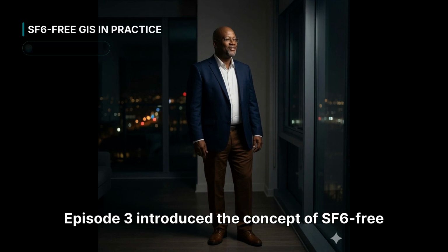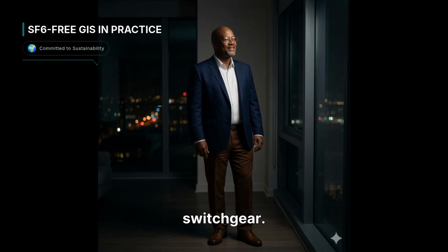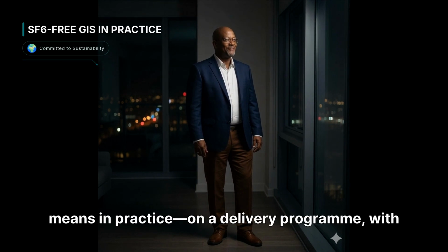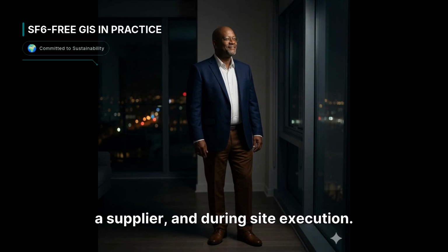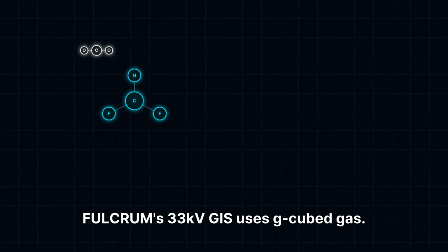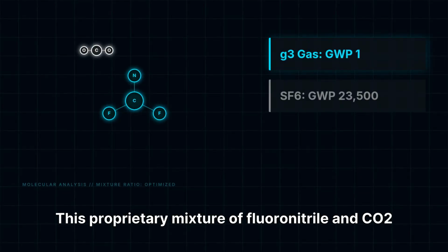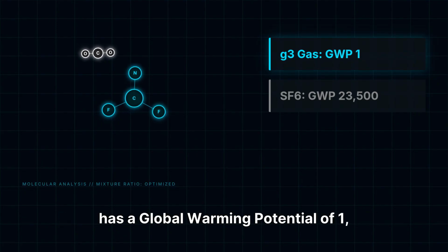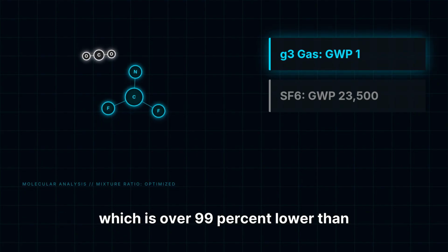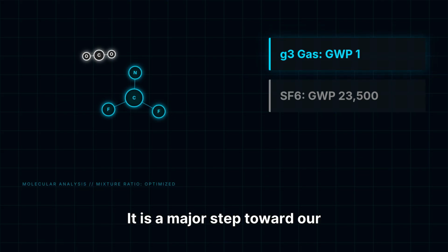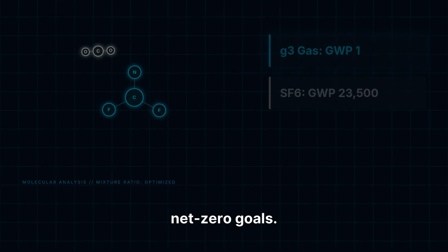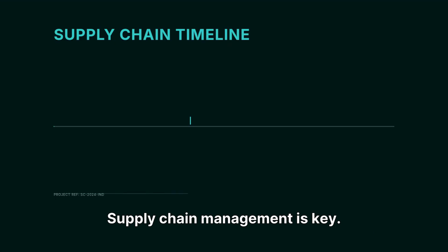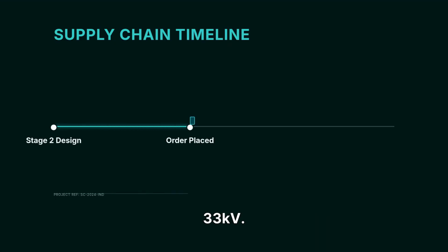Episode 3 introduced the concept of SF6-free switchgear. Now we look at what it actually means in practice on a delivery program, with a supplier and during site execution. FULCRUM's 33 kV GIS uses g3 gas. This proprietary mixture of fluoronitrile and CO2 has a global warming potential of 1, which is over 99% lower than traditional SF6. It is a major step toward our net zero goals. Supply chain management is key. Only a few manufacturers offer this at 33 kV.